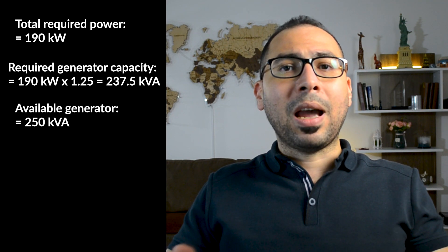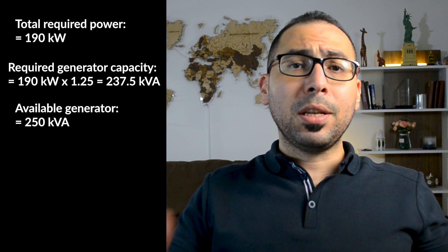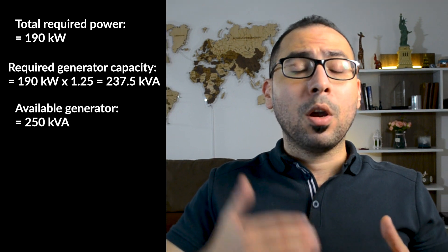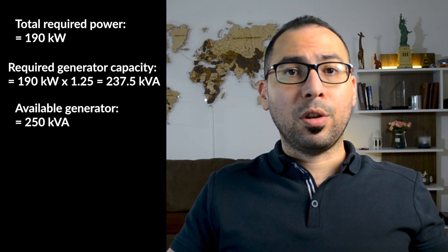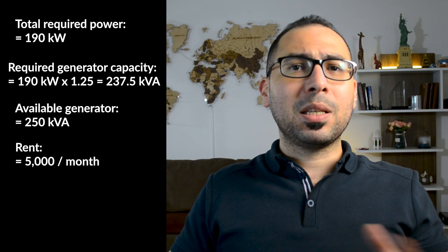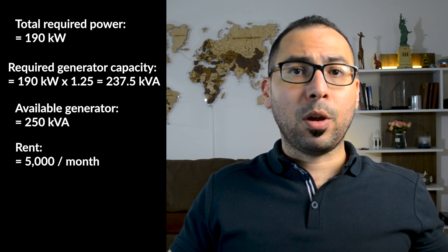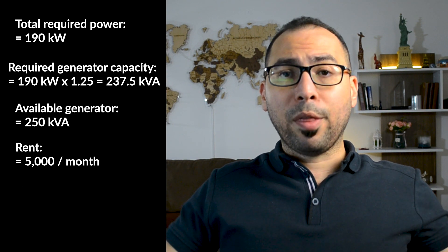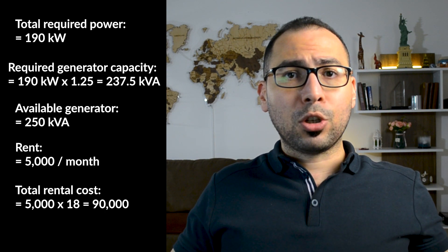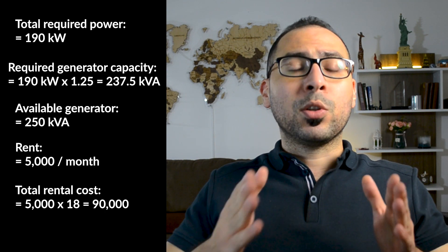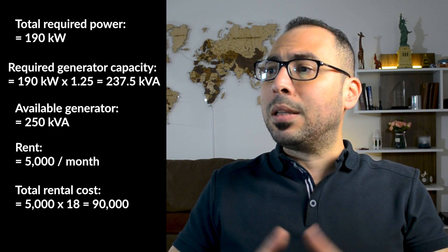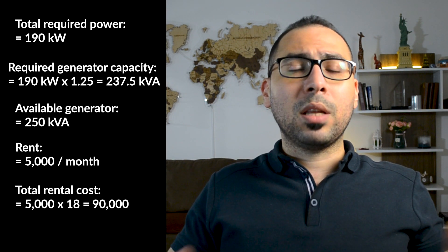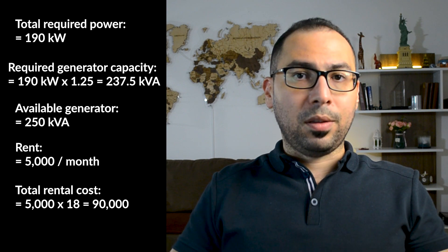Since I need 237 kVA, I'll go for a 250 kVA generator and rent it. Now I need to see how much the rental cost is. Let's assume it's 5,000 per month. If I need this generator for 18 months — the duration of the project — that's 5,000 multiplied by 18, which equals 90,000 just for the generator rental.